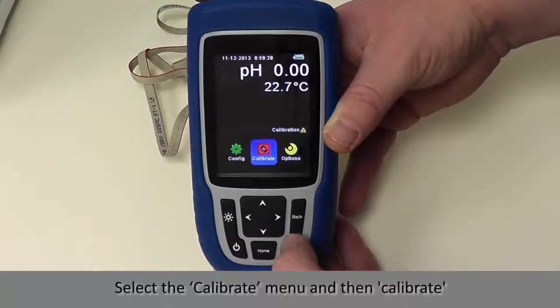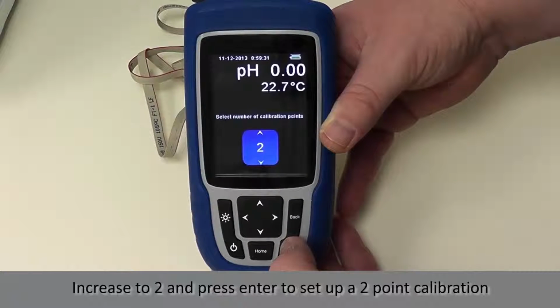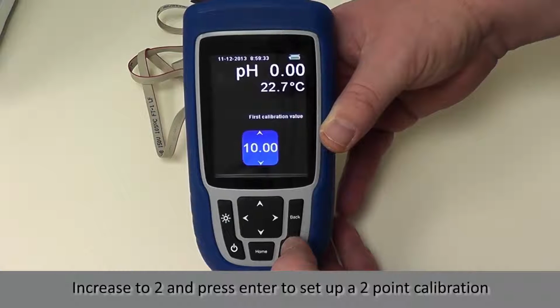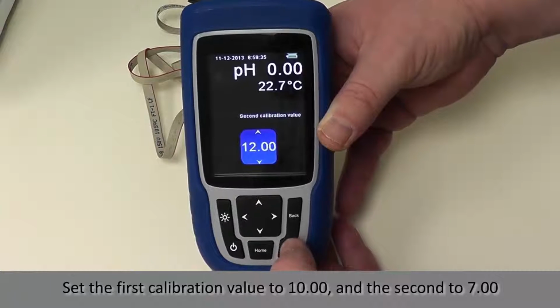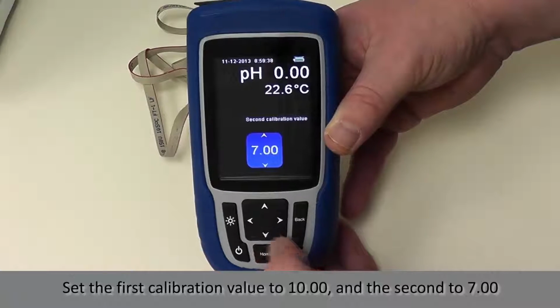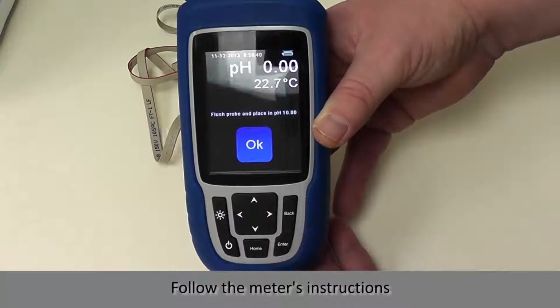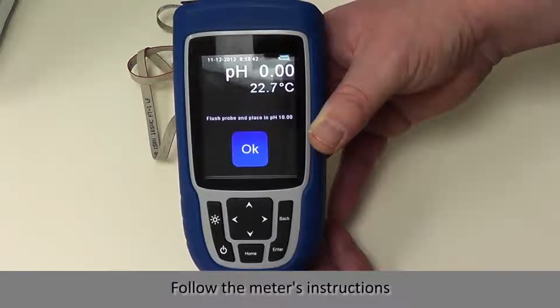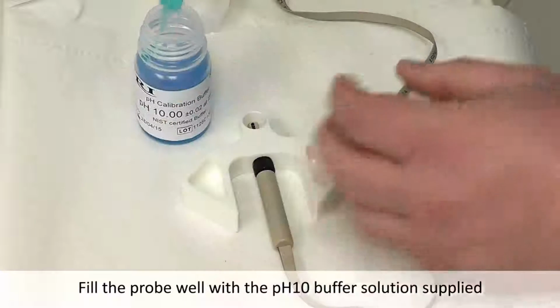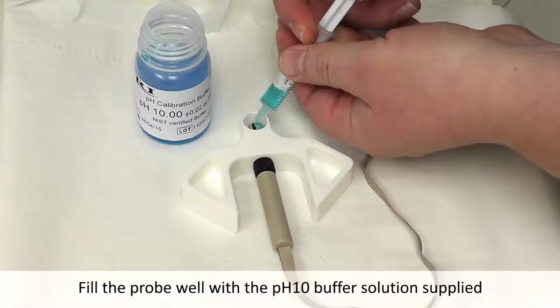Select the Calibrate menu and then Calibrate. Increase to 2 and press Enter to set up a 2-point calibration. Set the first calibration value to 10 and the second to 7. Follow the meter's instructions. Fill the probe well with the pH 10 buffer solution supplied.